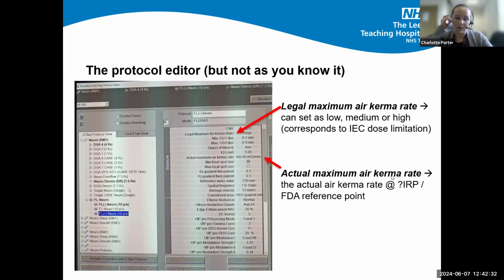So the other couple of things I wanted to pull out: the system for each protocol will set a legal maximum air kerma rate. I'm fairly sure this is low, medium, or high, and I think it corresponds to the different IEC dose limitation standards. This value of actual maximum air kerma rate, if I'm honest, I can't remember when I was putting this together this week whether that is specified at the interventional reference point or at the FDA reference point. That would be worth checking if you're wanting to actually test the dose rate limitation on the system.